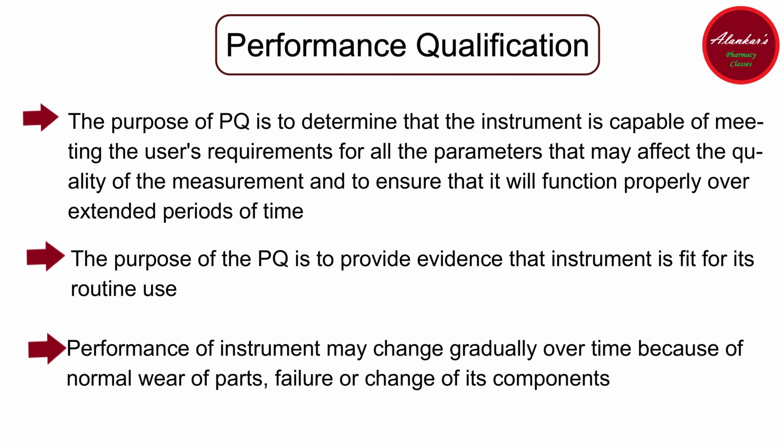Now the last part of the video is performance qualification. The purpose of PQ is to determine that the instrument is capable of meeting the user's requirements for all parameters that may affect the quality of the measurement, and to ensure that it will function properly over an extended period of time. The purpose of PQ is to provide evidence that the instrument is fit for its routine use.